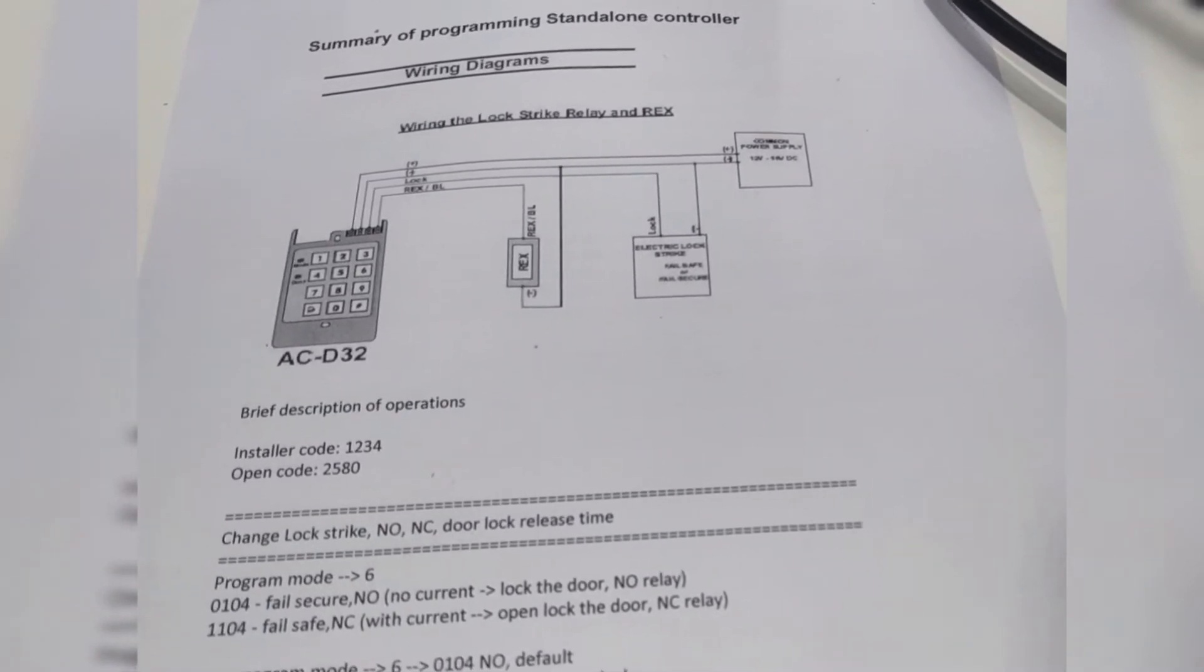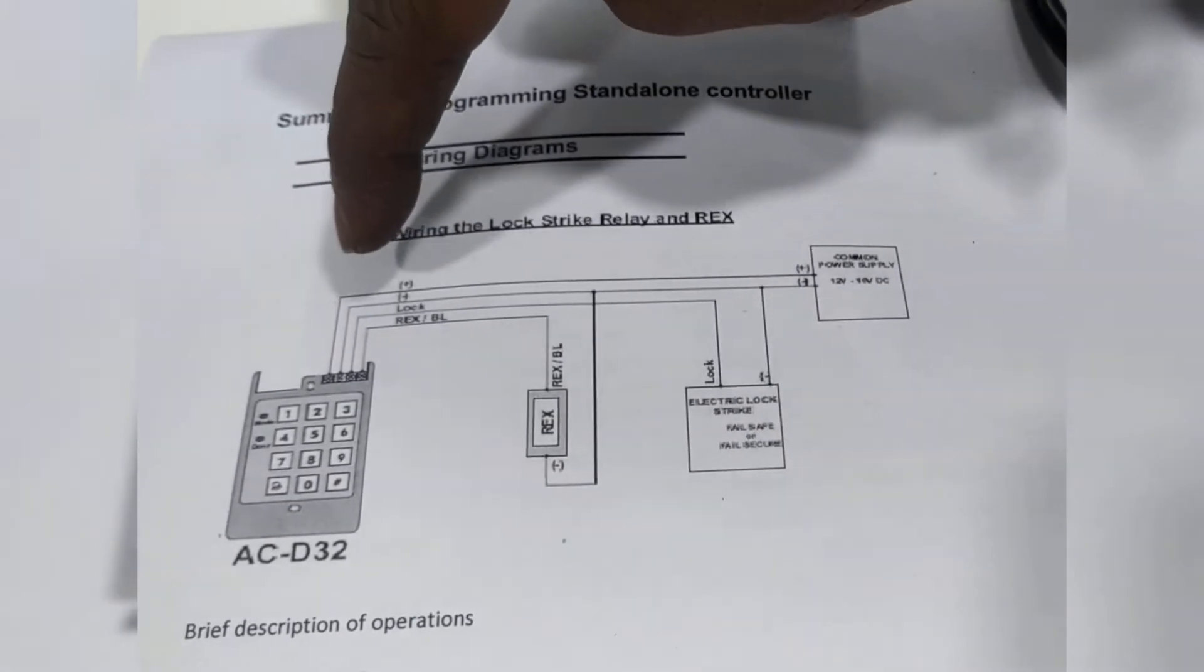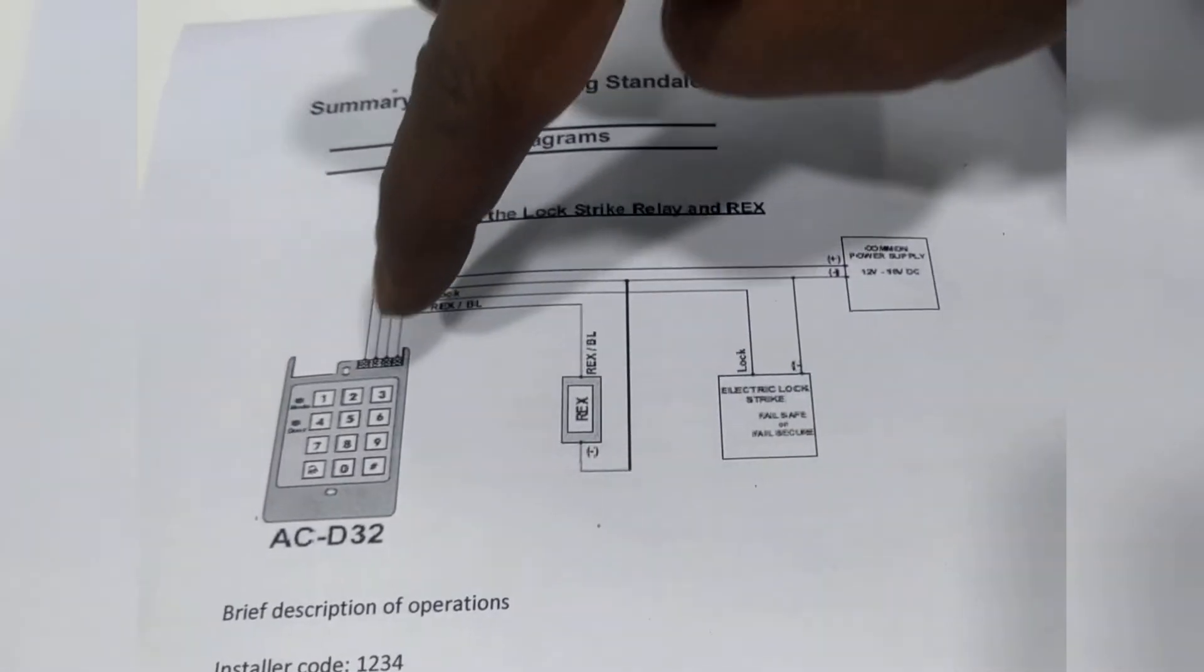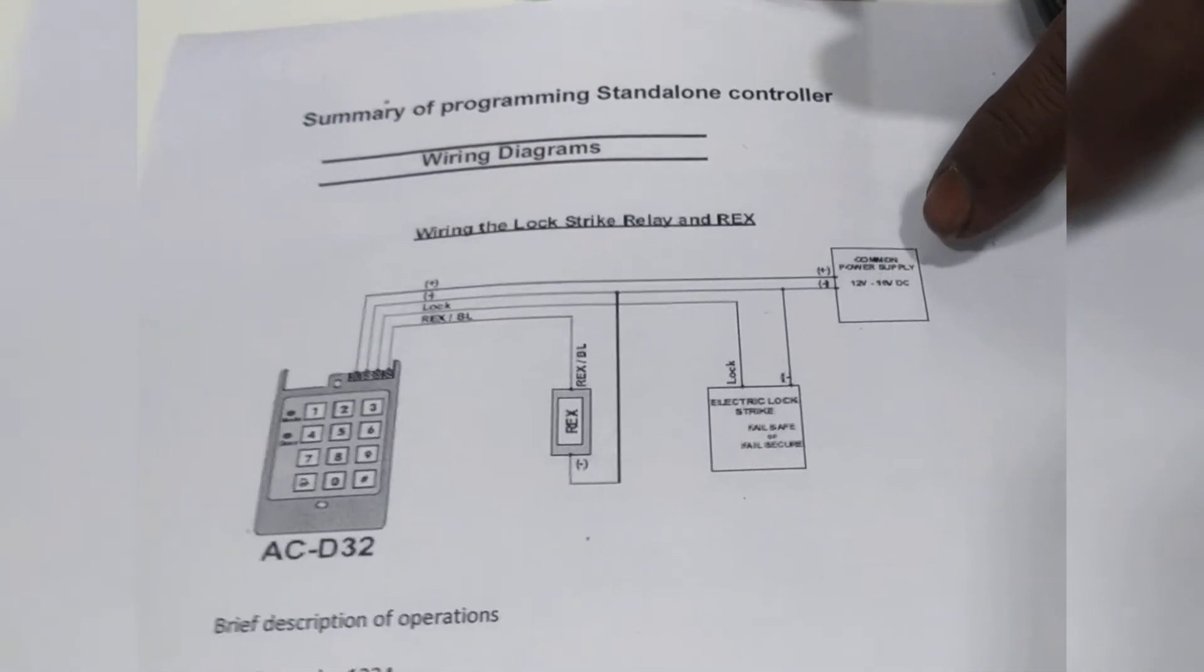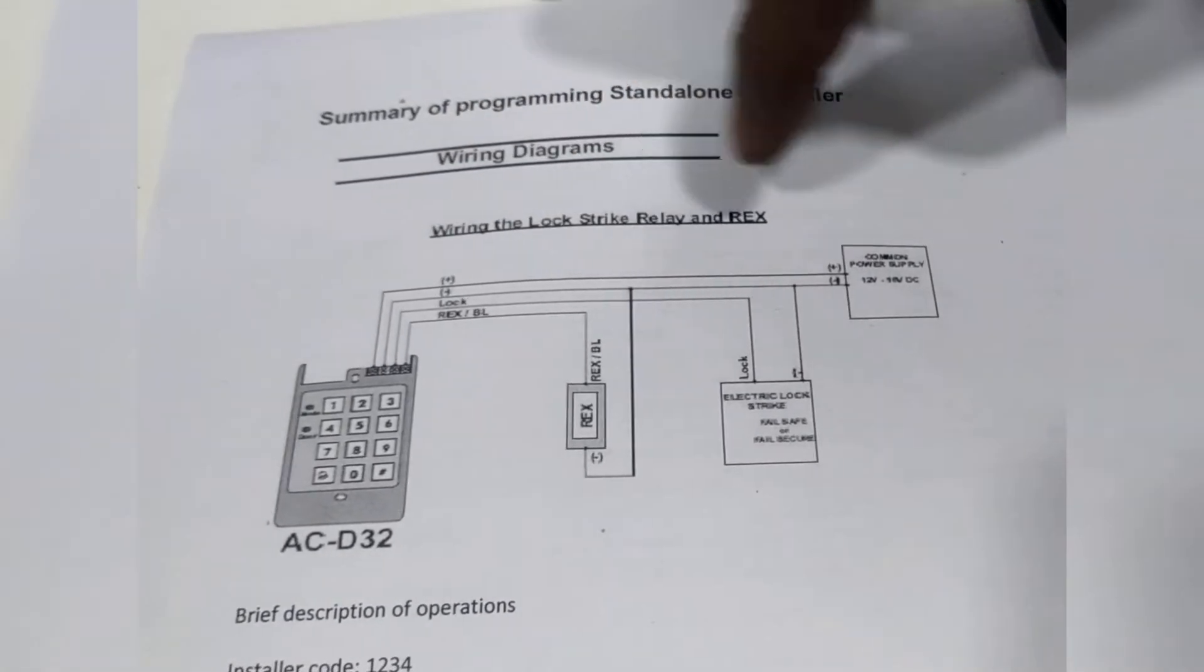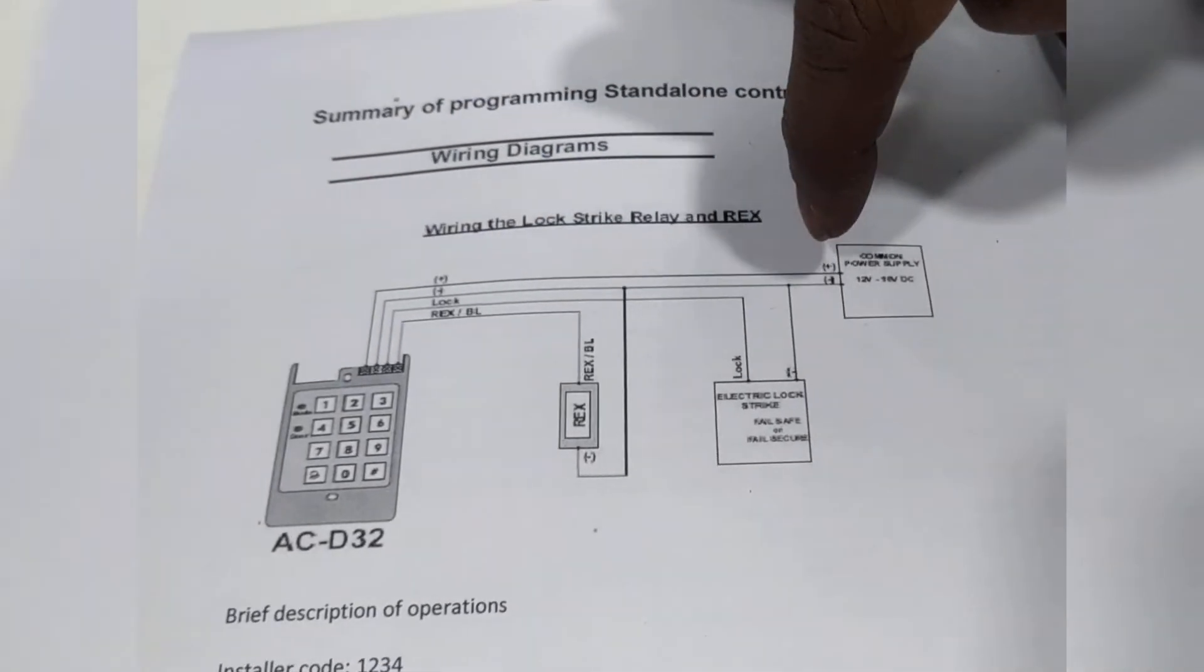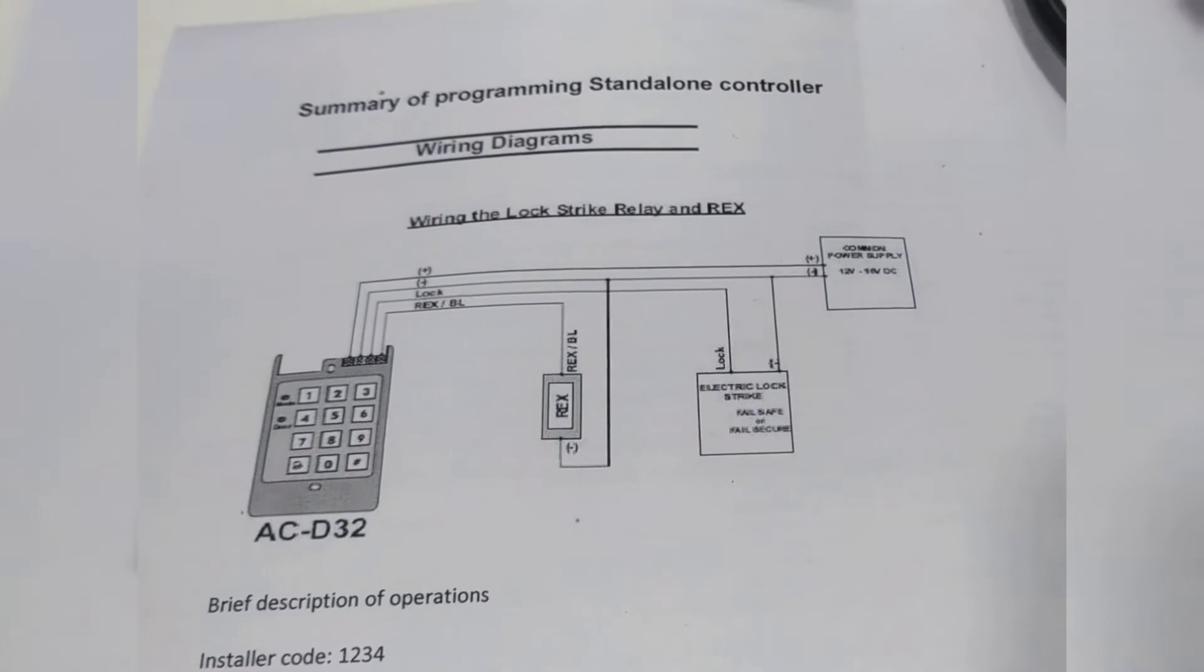This is the ACD32 controller and we can connect push button switch as well as EM lock. We have to provide the 12 volt DC power supply. So total four wire connectivity - entire system two for the power and ground is common for everyone, one from lock and one from push button switch.